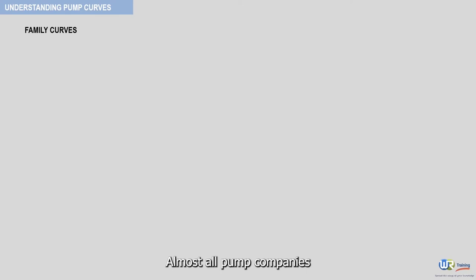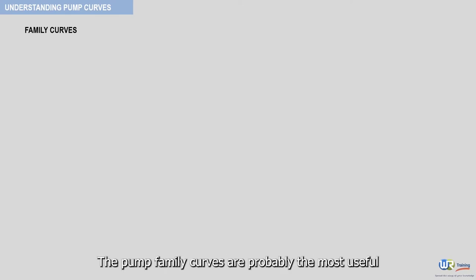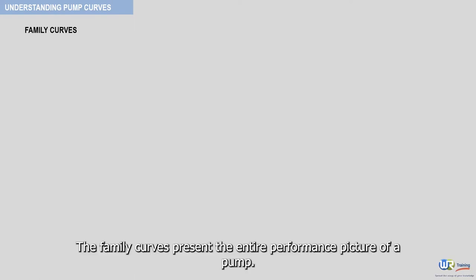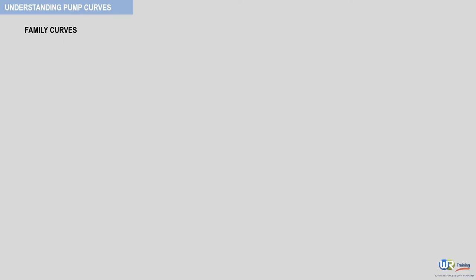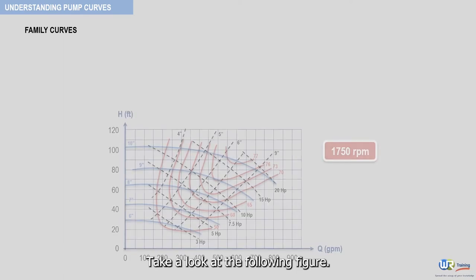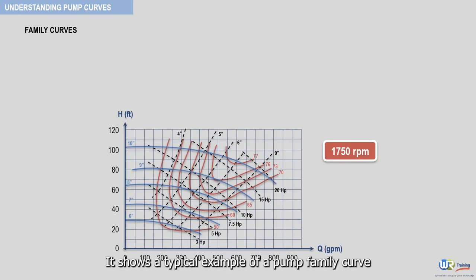Almost all pump companies publish what are called the family of curves. The pump family curves are probably the most useful for the maintenance engineer, the design engineer, and the purchasing agent. The family curves present the entire performance picture of a pump. Take a look at the following figure. It shows a typical example of a pump family curve.